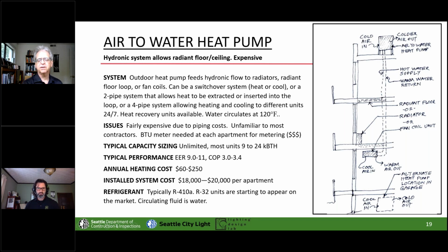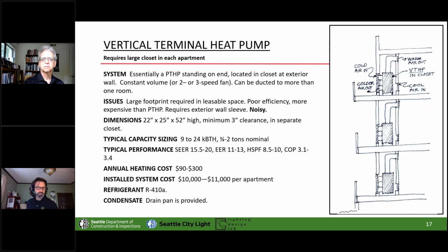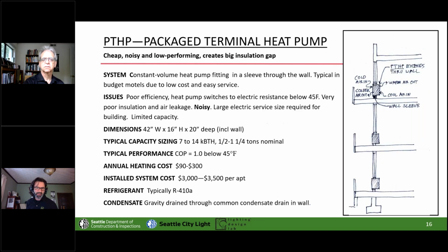So, and I've been here talking to manufacturers as we've got ready for these seminars, and everybody is hustling to try to get those to market because they might not care about Washington, but they really care about California. This is a volume thing, as well, volume of refrigerant. So in a packaged unit, most of what we've looked at here are packaged units, your quantity is small. You don't have to worry that it's a lightly flammable thing because you're below this magic number in the code, the maximum allowable quantity.